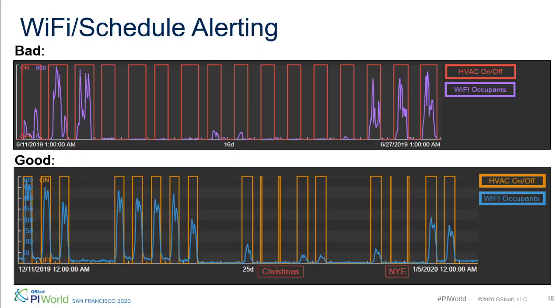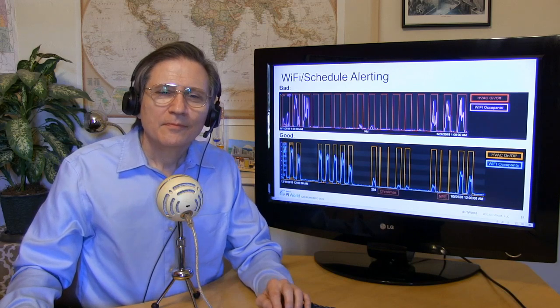Okay. You actually make use of Wi-Fi information to help you figure out what occupancy is like currently in the rooms. Where in the world did you get Wi-Fi data, and how did you bring it into the Pi system? So the campus has a way of accessing the current 15-minute count for all the different Wi-Fi hotspots on campus, which are generally named by building and fairly discernible in what they mean. So that was available, and we were able to pull that from a website, and we're using the UFL connector to do an HTTP get of that. Maybe I didn't use quite the right term, but we're getting that from the website using the UFL connector, and then that parses it and goes into Pi.